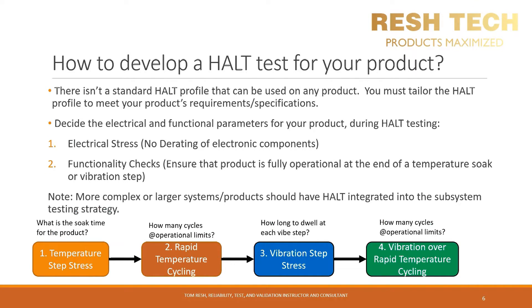So how do we develop a HALT test for a specific product? I must warn you that there is not a single plug-and-play profile for HALT testing on any product. You must develop a HALT profile specifically around your product's requirements. You need to determine the electrical and functional parameters and requirements that will be utilized for the HALT testing. One option is to run the PCBA or electronic devices at max loads with zero derating, combining electrical and thermal stress from the device itself with the ambient temperature conditions simulated in the HALT chamber.